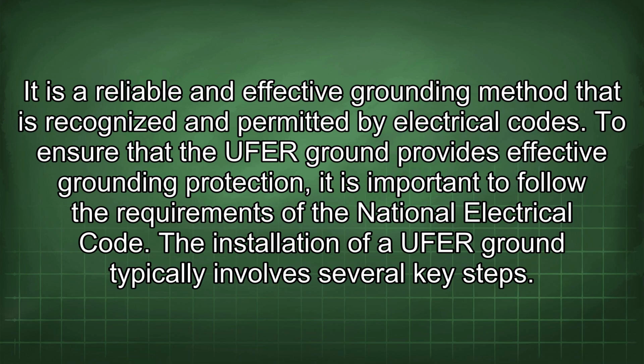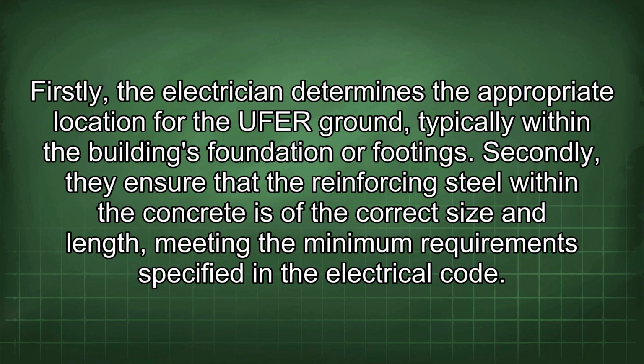To ensure that the UFER ground provides effective grounding protection, it is important to follow the requirements of the National Electrical Code. The installation of a UFER ground typically involves several key steps. Firstly, the electrician determines the appropriate location for the UFER ground, typically within the building's foundation or footings. Secondly, they ensure that the reinforcing steel within the concrete is of the correct size and length, meeting the minimum requirements specified in the electrical code.